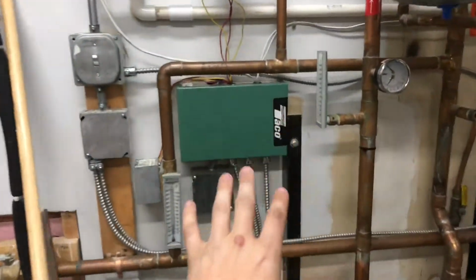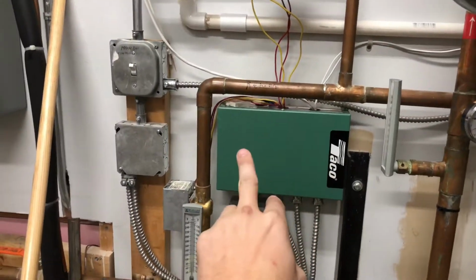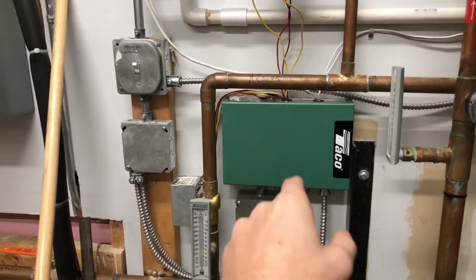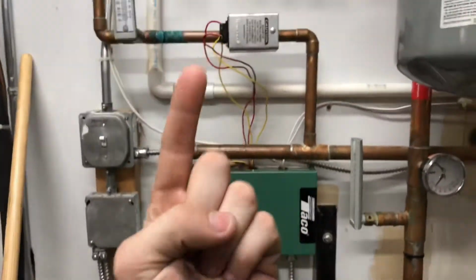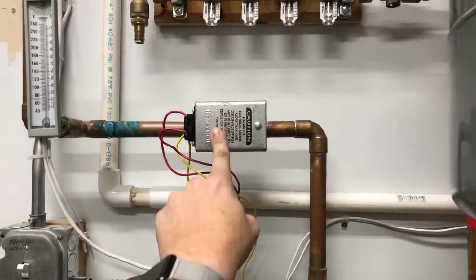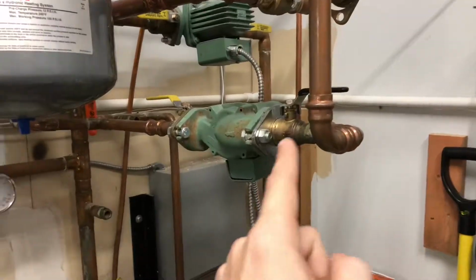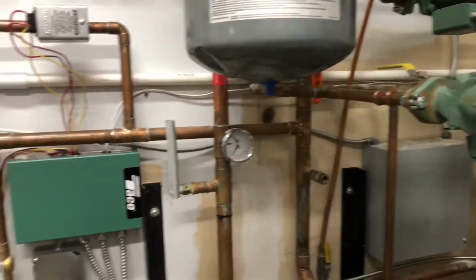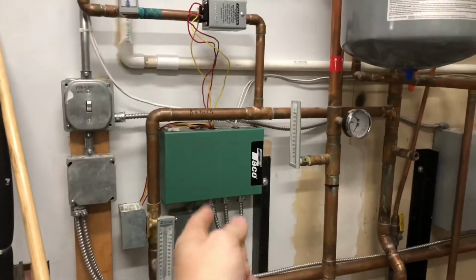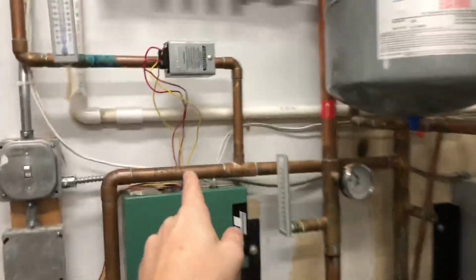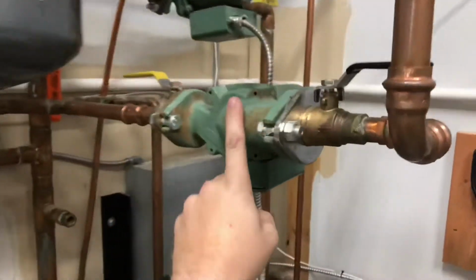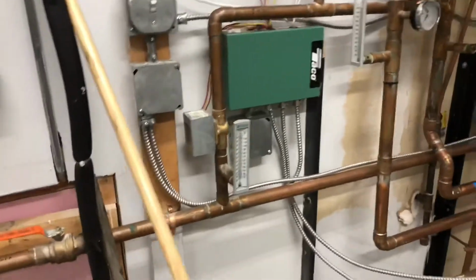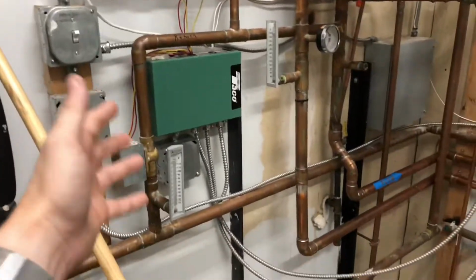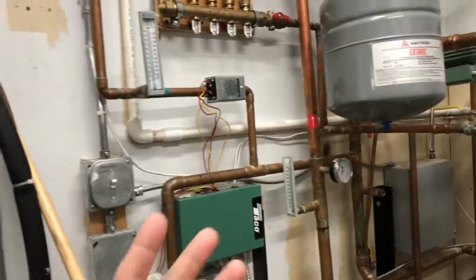So there's a separate relay in here for zone 1 and zone 2. The only thing this thing does is takes a signal from your thermostat and it engages the low voltage zone valve and the high voltage pump at the same time for that one particular zone. So when the thermostat tells this board to fire zone 1, all it's doing is opening this valve and firing this pump up, as well as sending a regular thermostat signal to the boiler to fire it up as well. So that's the same for zone 1, zone 2. There's just another zone valve for zone 1.